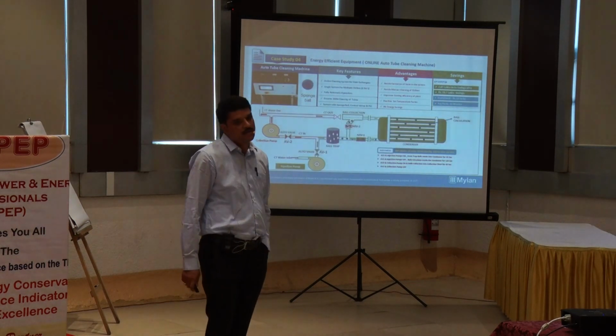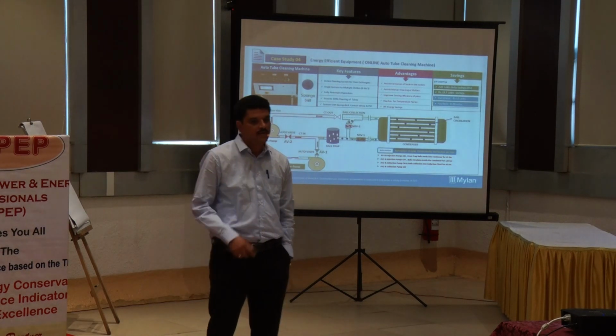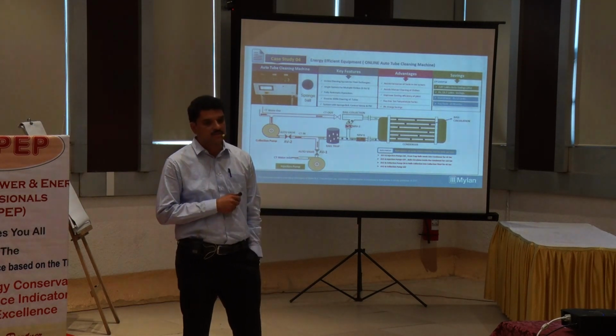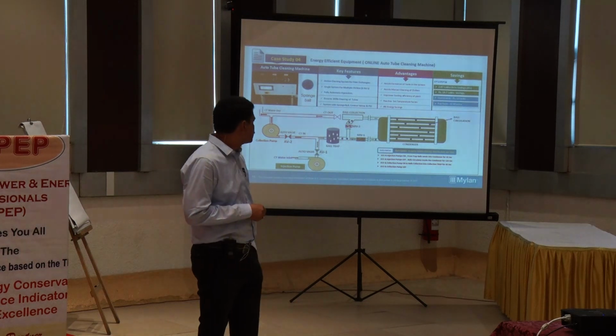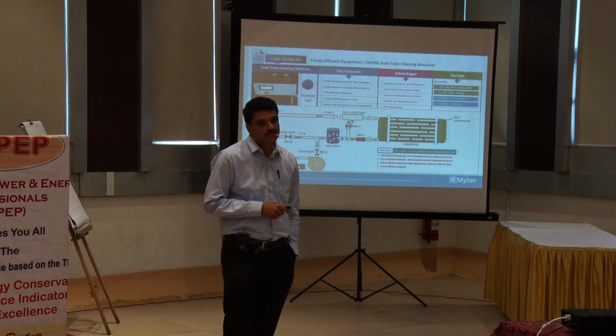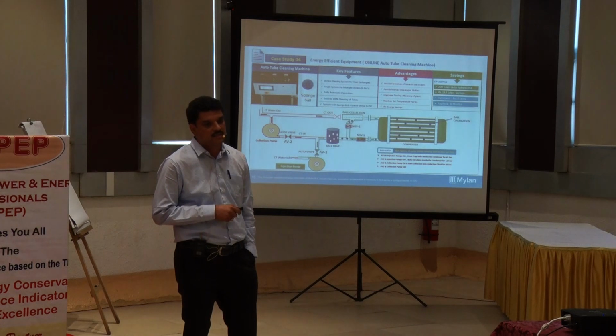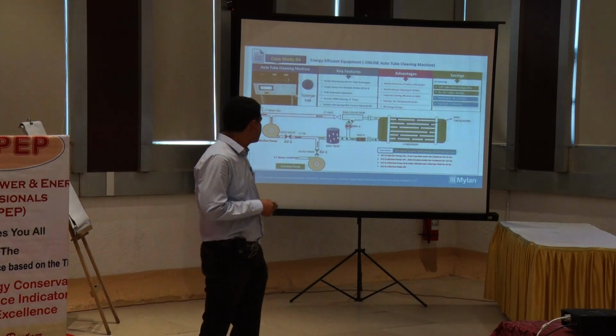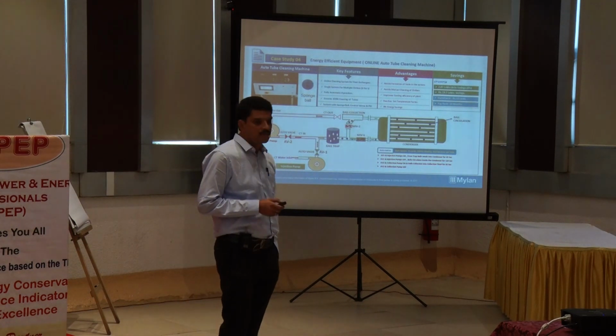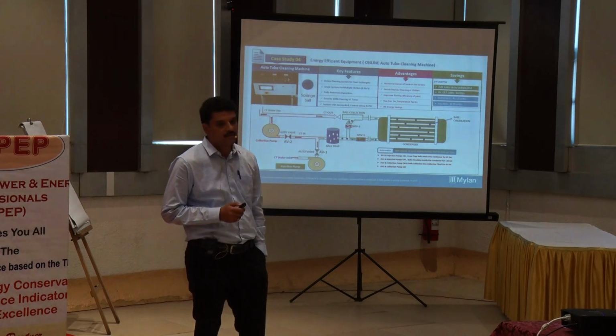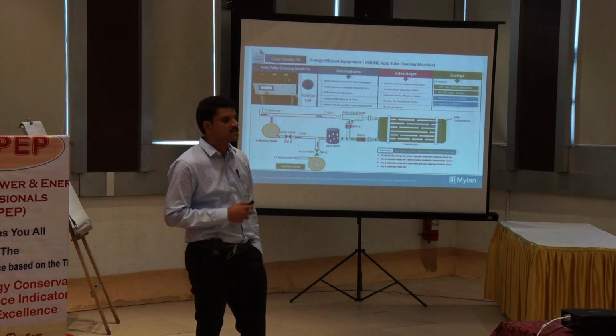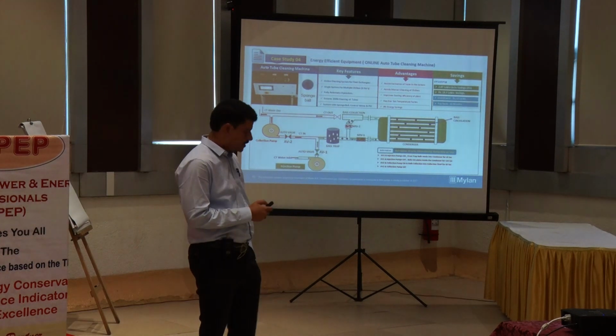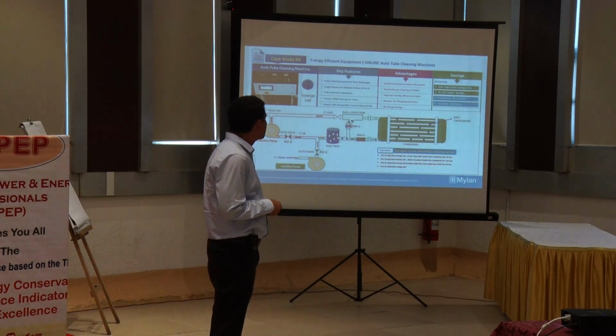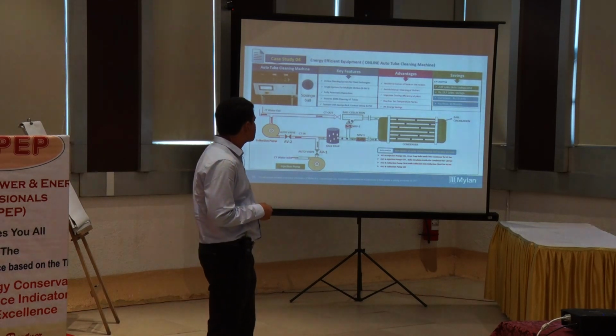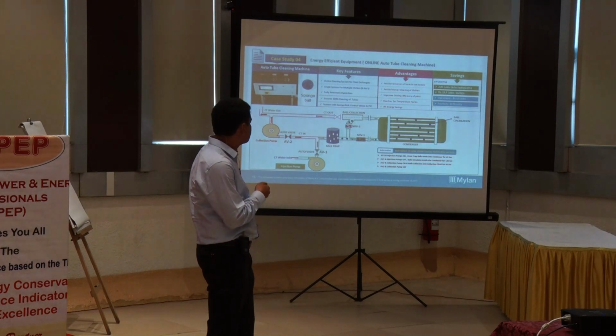So we have installed online tube cleaning system for all chillers. 6 chillers we have installed. So earlier we used to have manual cleaning system. Once in 3 months we used to clean the heat exchanger of the chillers. With this system, we are able to clean the heat exchanger twice in an hour. Each condenser, the online system is cleaning twice in an hour. With this, efficiency is improved, and we have saved 8 to 12% power. The investment is 12 lakhs and payback is 10 months.